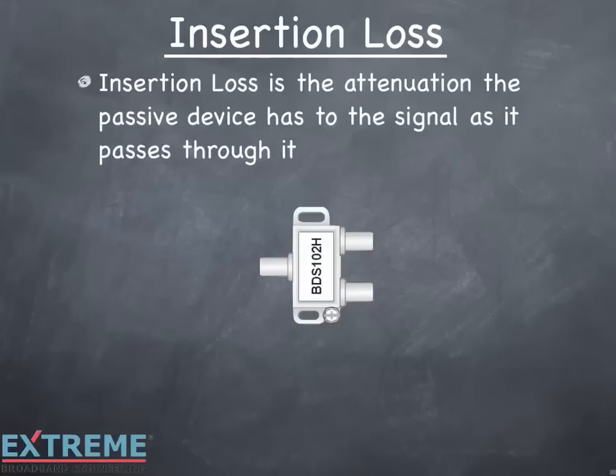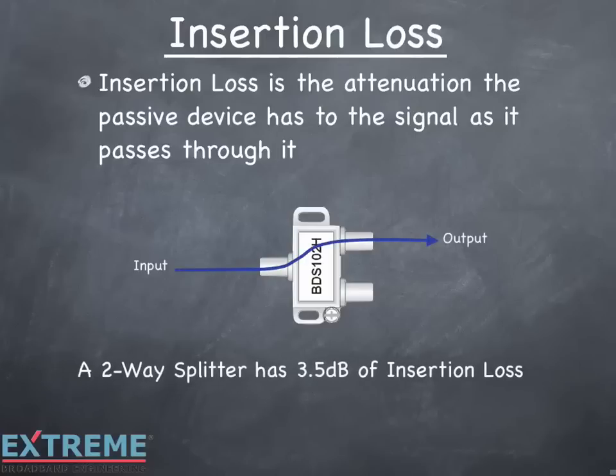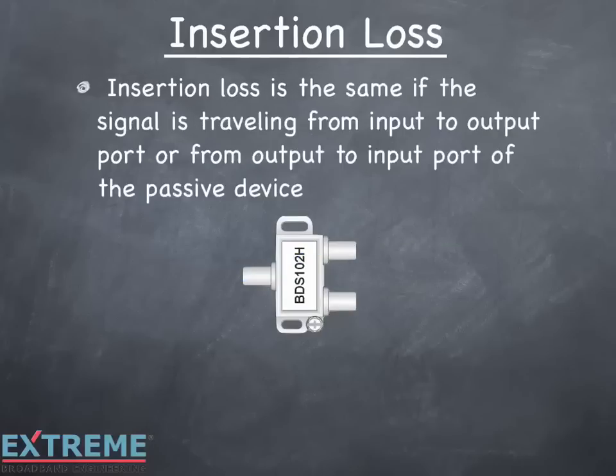Insertion loss is the attenuation the passive device has to the signal as it passes through it. Here we're showing a signal flowing from the input to the output of a two-way splitter. A two-way splitter has 3.5 dB of insertion loss. Insertion loss is the same if the signal is traveling from the input to the output ports, or from the output ports to the input port of the passive device.